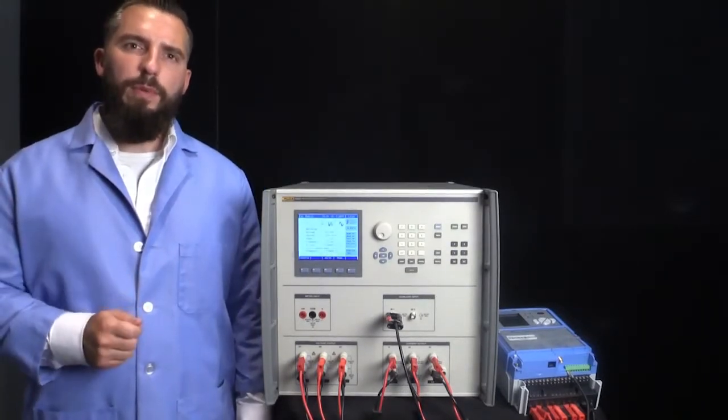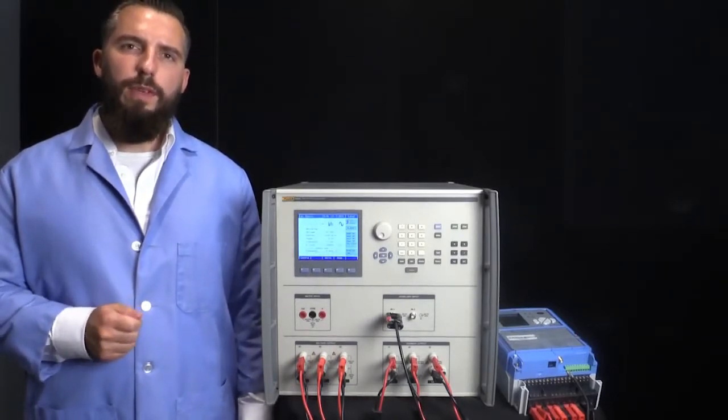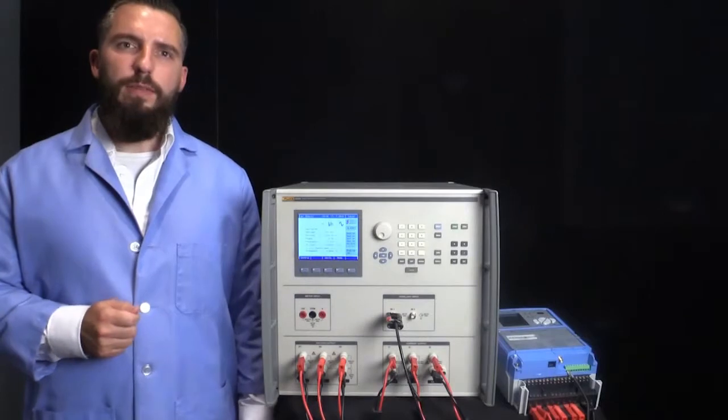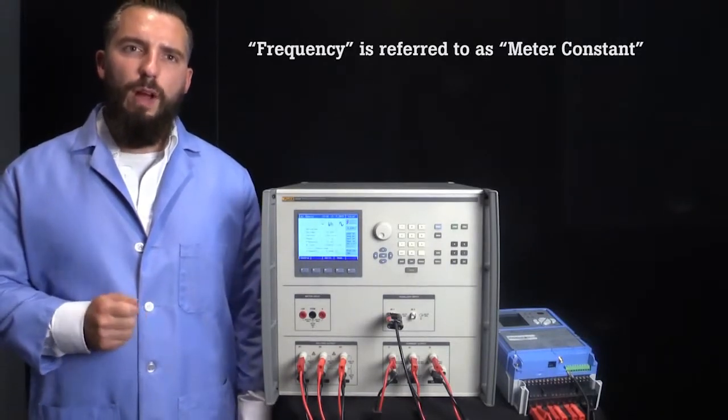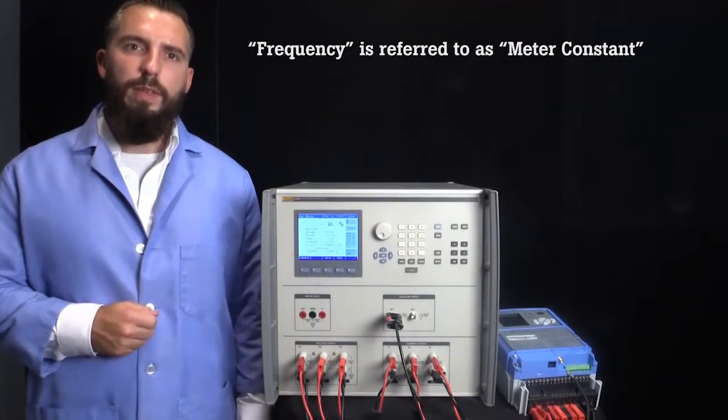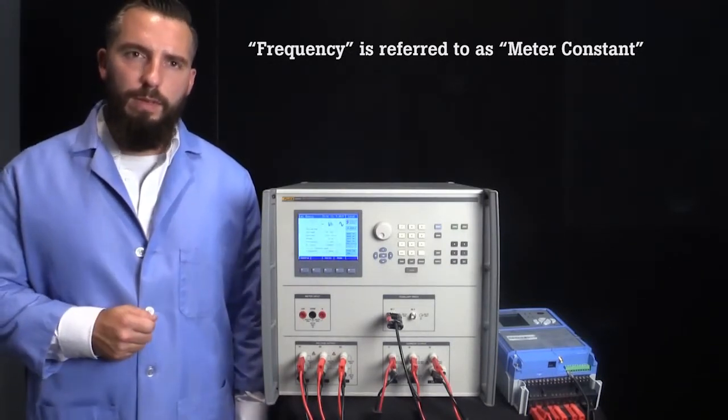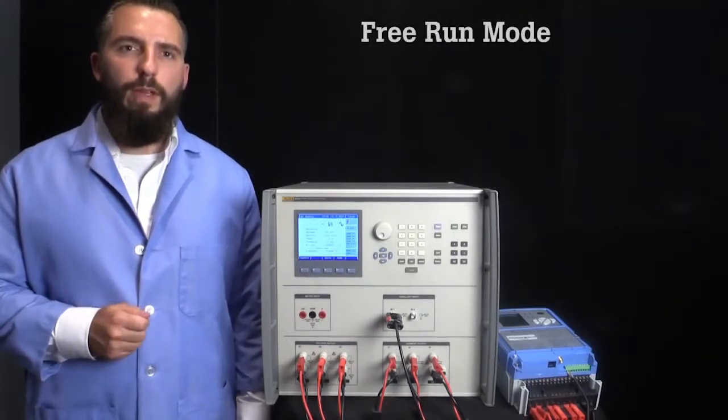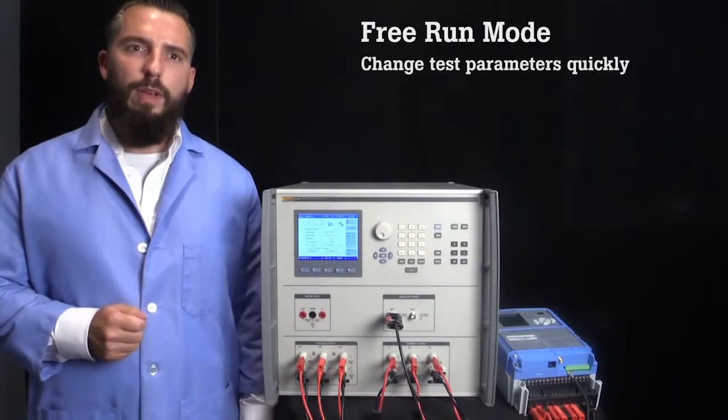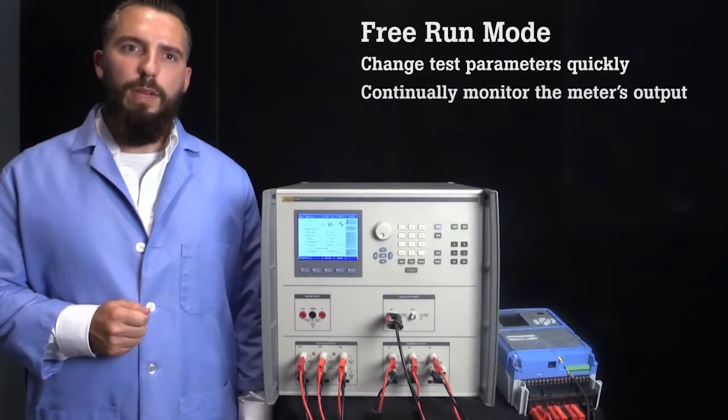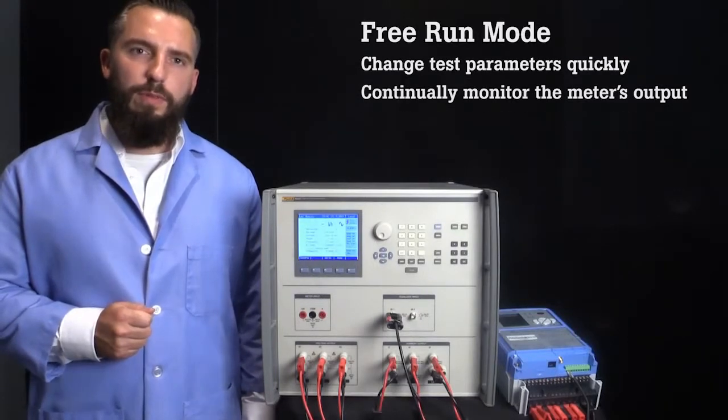One of the biggest pain points in energy meter calibration is determining what the correct frequency of the meter output is, based on the energy it is measuring. For reference, the frequency is also commonly referred to as the meter constant and matching the meter constant to the calibration system can be confusing. The 6003A has a mode called Free Run that simplifies this process and allows you to quickly change the test parameters by continually monitoring the meter's output to verify that the correct meter constant is being used.